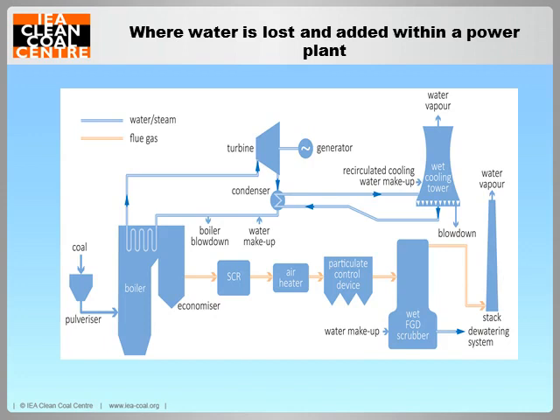Now, water exits the system in various ways. These include the unavoidable losses. For example, part of the recirculating water in the cooling tower evaporates and the resultant water vapour is lost to the atmosphere when it exits through the top of the tower. There are also losses in the formation of products such as gypsum from the wet flue gas desulphurisation scrubber. And blowdown is another loss. Blowdown is necessary to preserve water quality and to remove impurities from the various recirculating streams. This includes the boiler feed water, FGD streams and cooling water. And then water is also lost when handling products such as in ash sluicing.